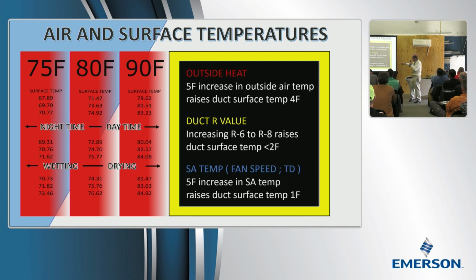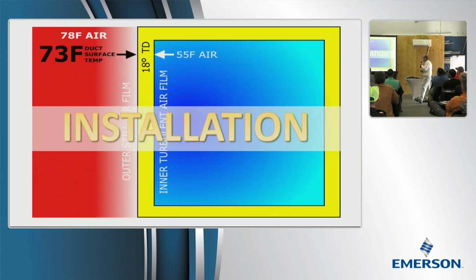And then the one that everybody does because it's cheap, it's easy, whether it works or not, for every 5 degrees that you decrease your TD is basically what you're doing. Hopefully you're manipulating fan speeds and not refrigerant charge or something goofy. But if you're just changing the fan speeds and you can get a 5-degree rise, that'll get you 1 degree. But it has a lot to do with how it's installed.